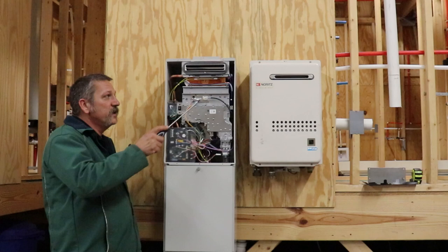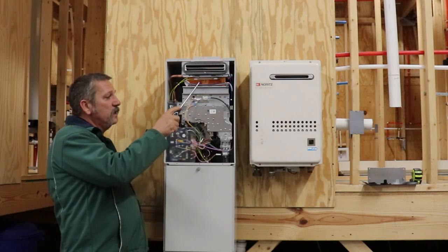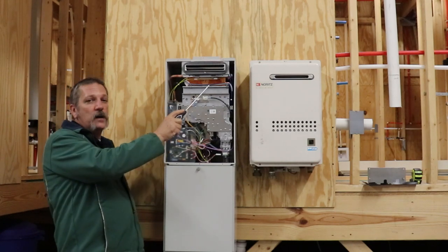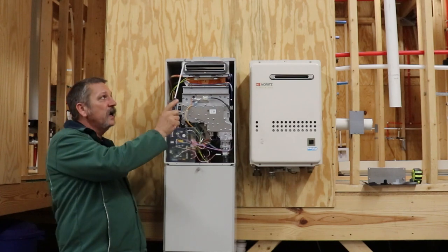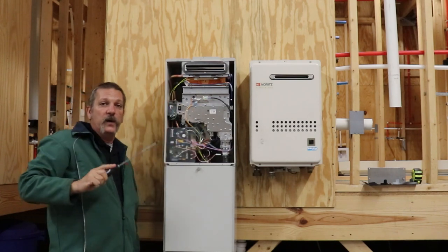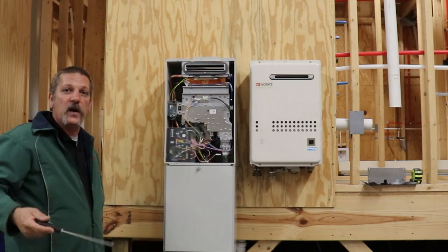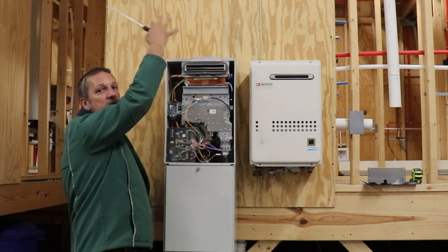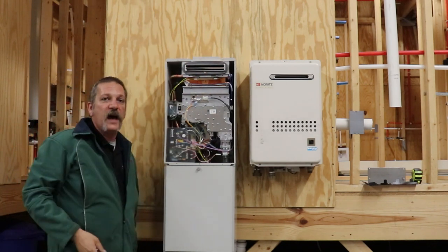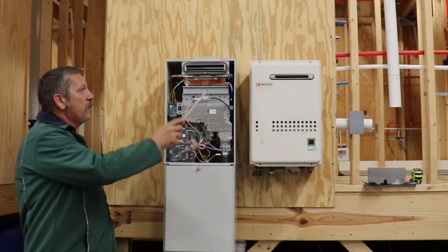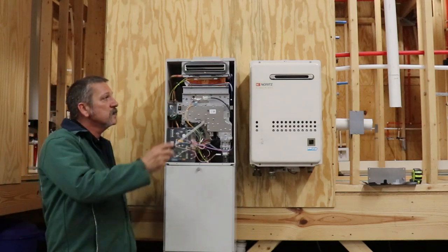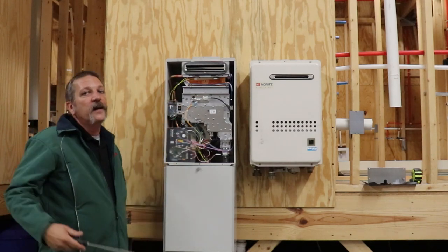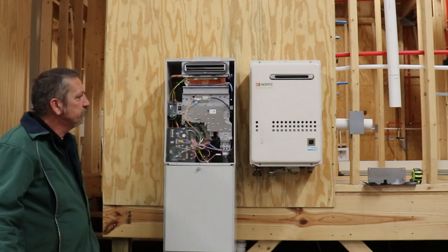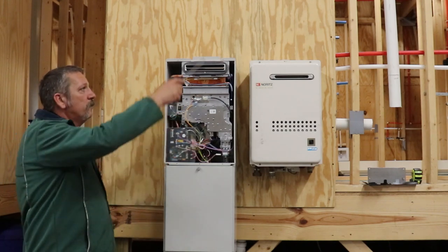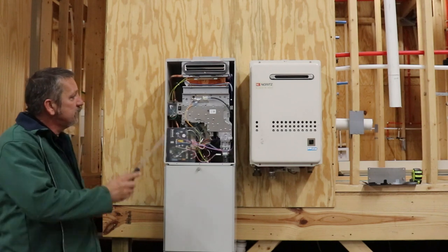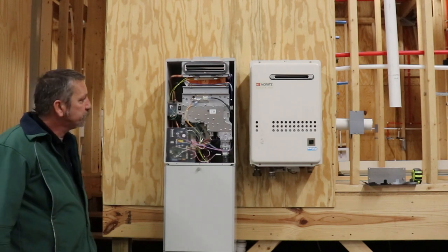But since this heat exchanger is sitting right on top of here, hot gas is going up, any kind of moisture, anything that would get in there is being blown out the front. Sometimes on a really damp day, like a rainy day or whatever, you might see steam just blowing out of that. And that's perfectly normal, just to have some little steam coming out of it, because it's burning that moisture off in there. That's why it's non-condensing. It's cooking that moisture out and blowing it back out into the air. But that's basically how this one works.